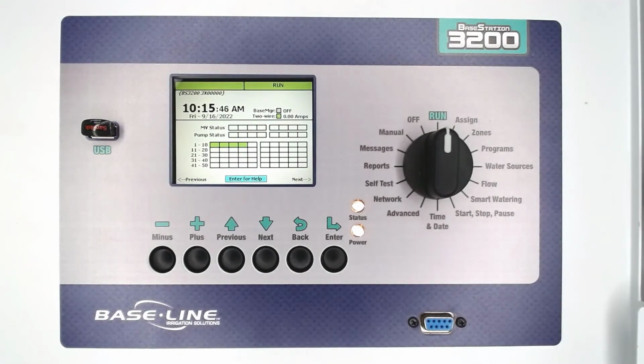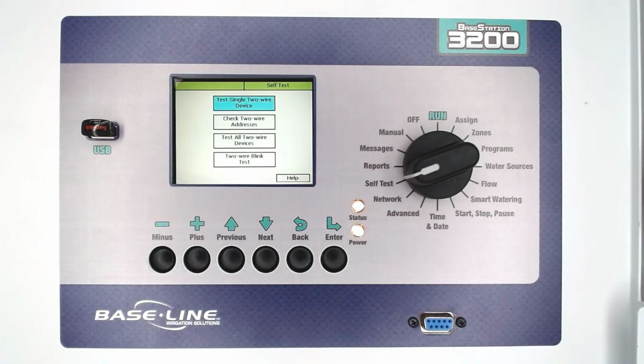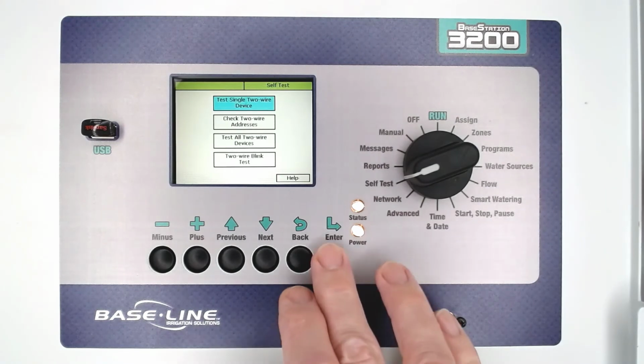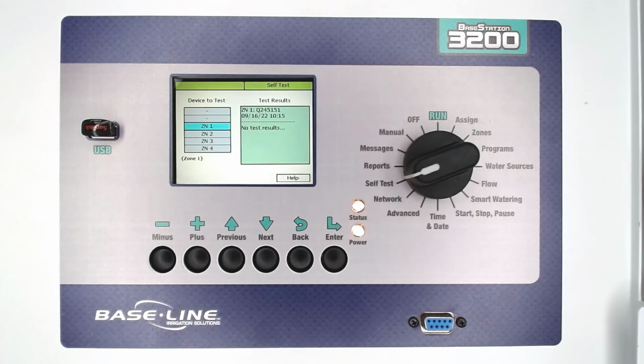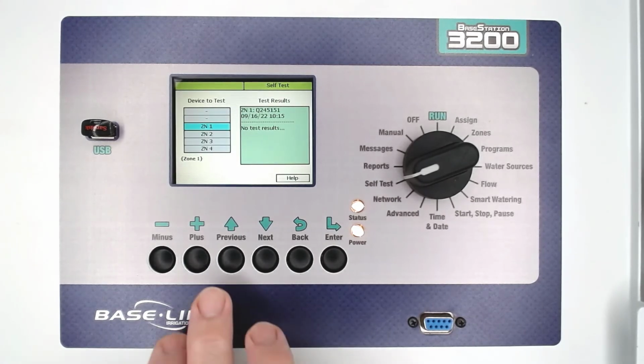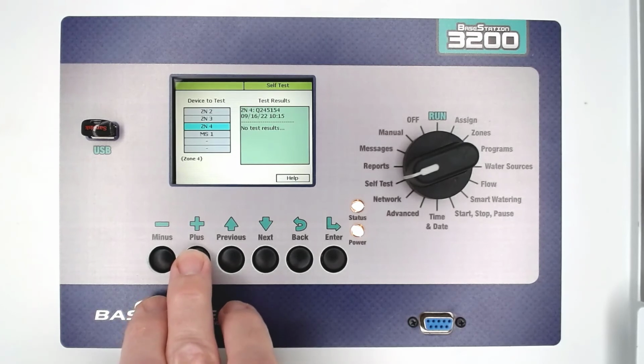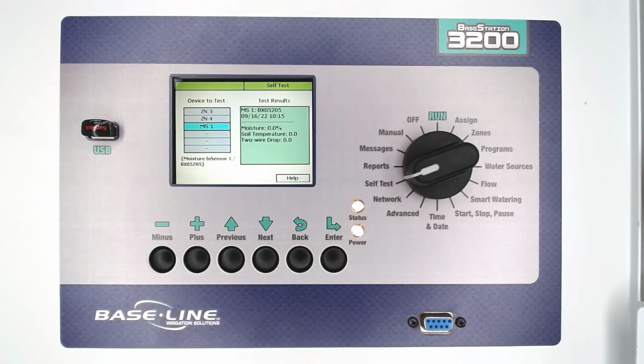From the controller, turn the dial to the SelfTest position. Highlight the menu Test Single Two-Wire Device and press Enter to open that menu. Here I can test any device that's been assigned during the search and assign process. Scroll through the list until you find the device you want to test. In this case, it's Moisture Sensor 1. With MS1 highlighted, press Enter to start the test.